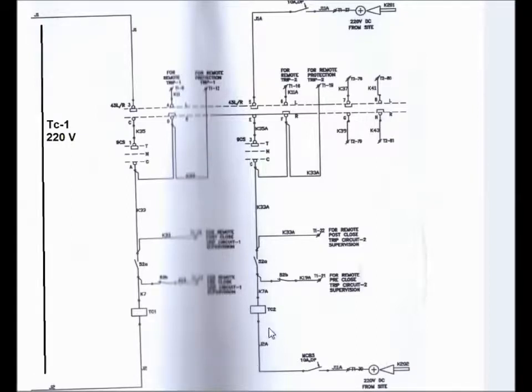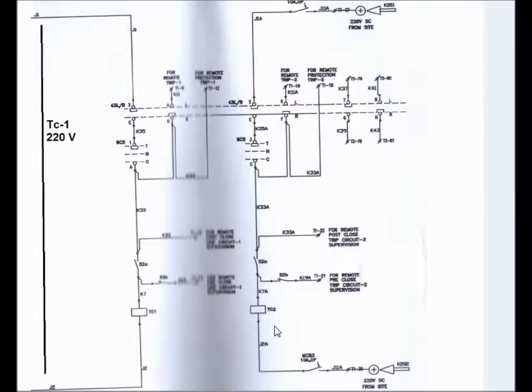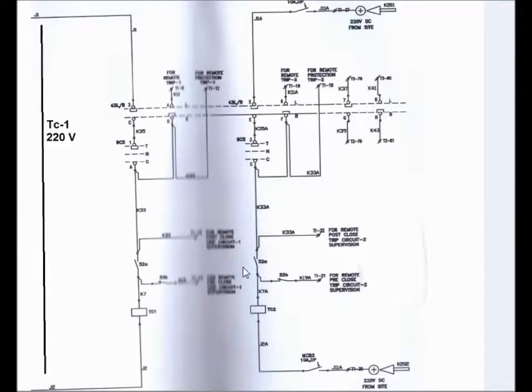Similarly for TC2, that is trip coil 2: for local operation, the local-remote selector switch must be in local position. If we give the tripping pulse, trip coil 2 will energize and the breaker will trip. For remote operation and for protection trip to TC2, this is the path through the trip coil 2.